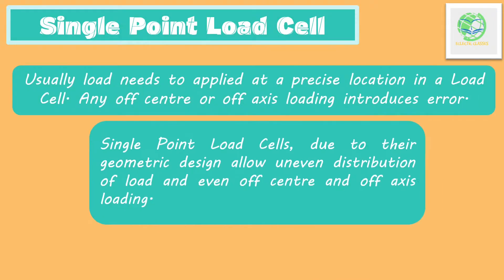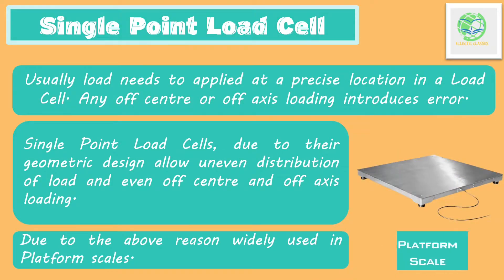Usually in load measurements, the load needs to be applied precisely at a specific location. Any deviation in terms of off-center or off-axis loading results in error. Single point load cells overcome this problem — due to their geometric design, they allow flexibility in getting accurate readings even if the load is applied off-center, off-axis, or is unevenly distributed. For this reason, they are most widely used in platform scales.